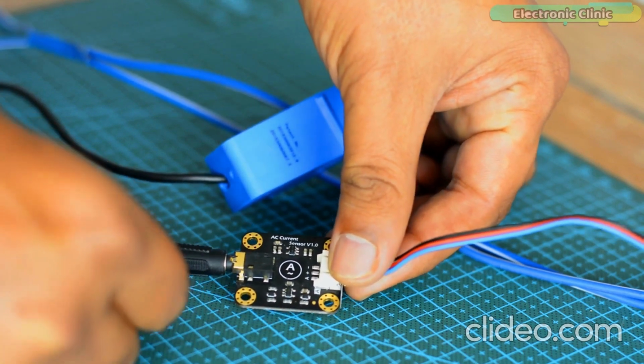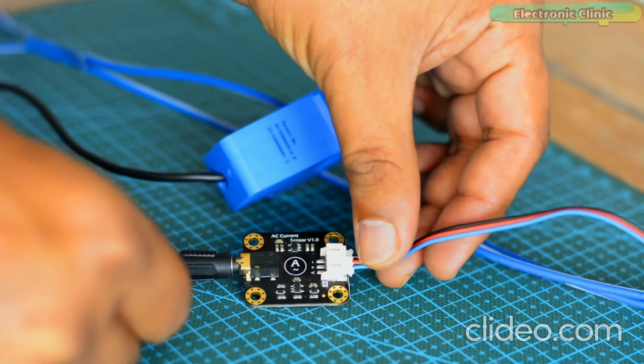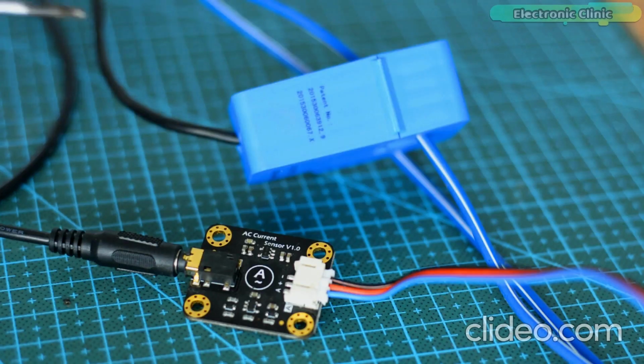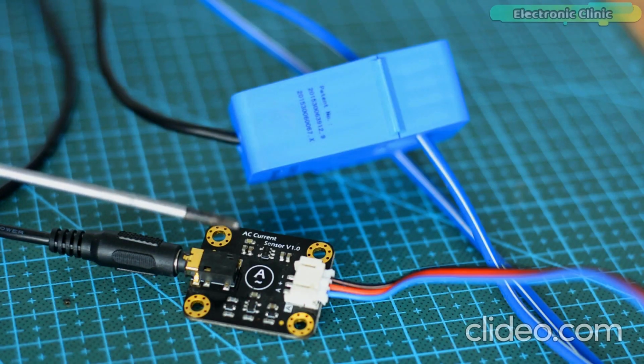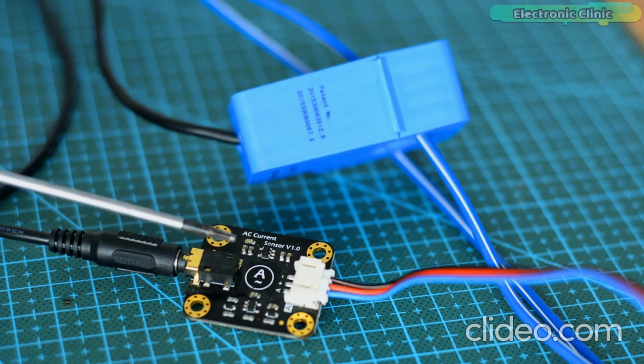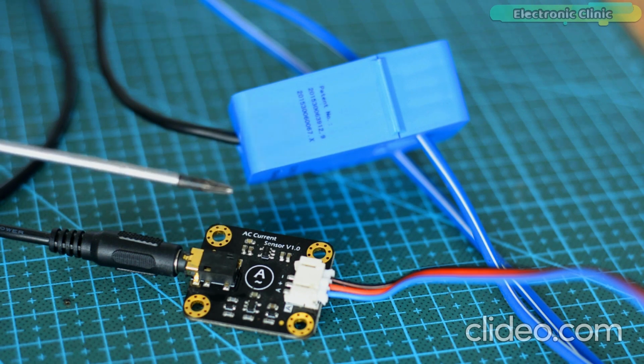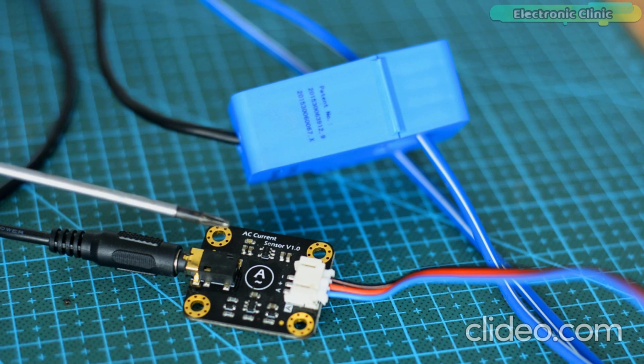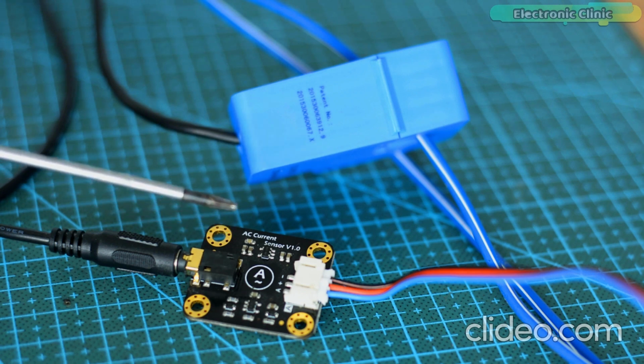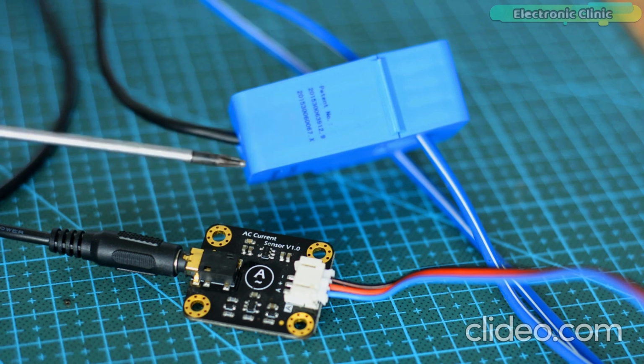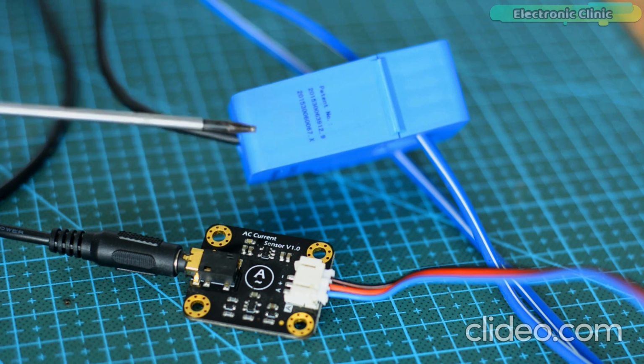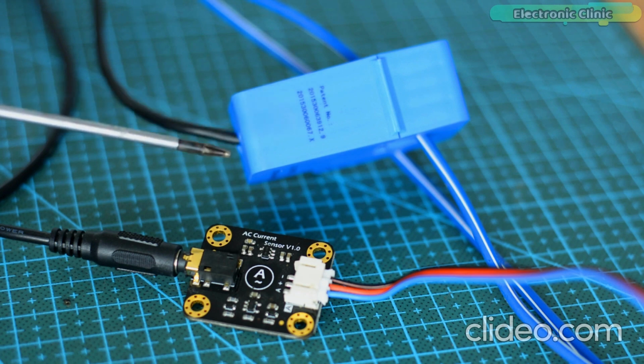The current transformer measures the current flowing in the live wire. If the total current detected by the current transformer is significantly different from the expected value, which should be 0 in an ideal case, it implies there may be a leakage. The current transformer generates a small alternating current in its secondary winding that is proportional to the current in the live wire. The output is typically a low voltage AC signal.